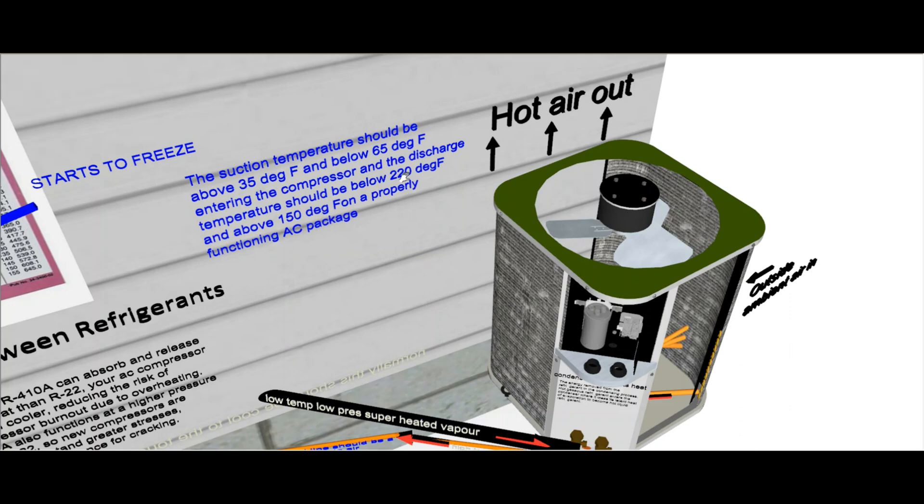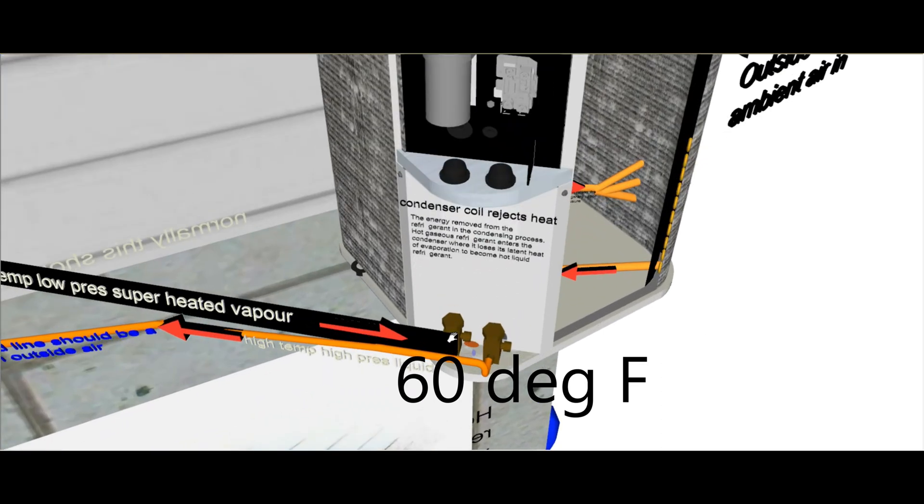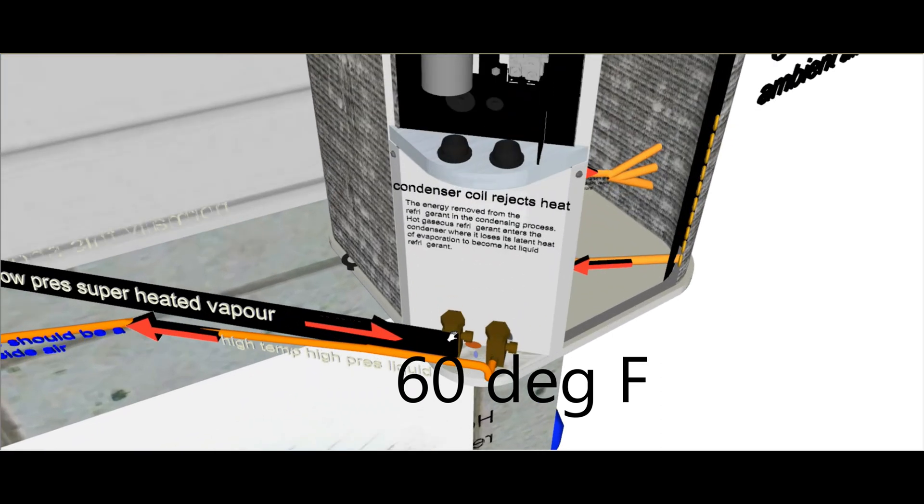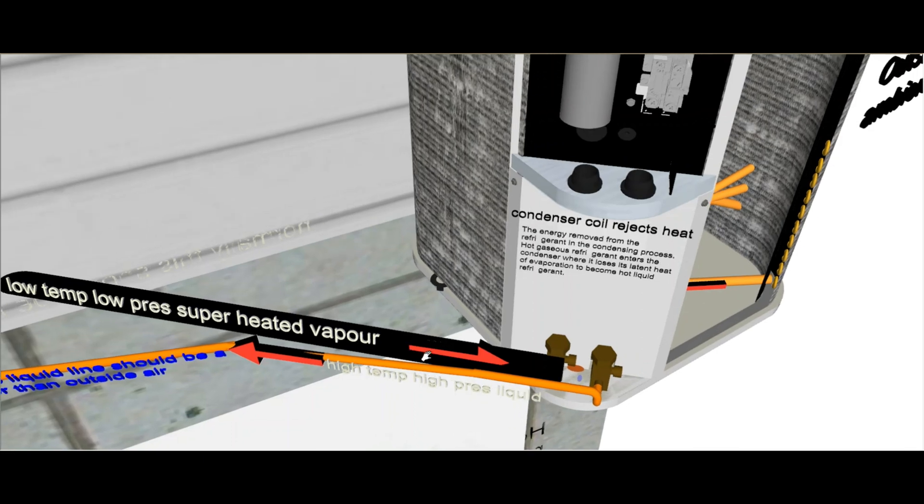The suction temperature should be above 35 degrees Fahrenheit and below 65 degrees Fahrenheit. So typically this one will be about 60 degrees, maybe lower but around 60 degrees. So it's cool to the touch if you touch it, even though it's a vapor, because this refrigerant has a lower boiling point, so that's why it's good for manipulating temperature and pressure. So only 60 degrees Fahrenheit coming in, we still call that a superheated vapor even though it's low temperature and low pressure.